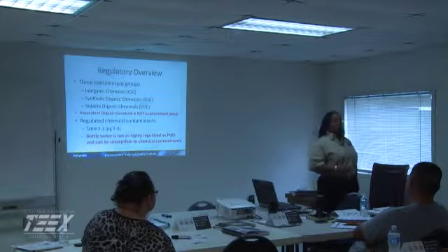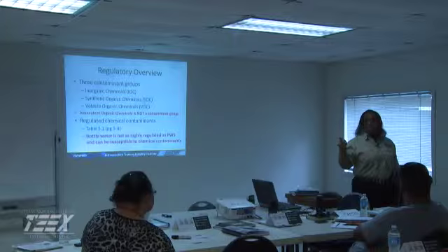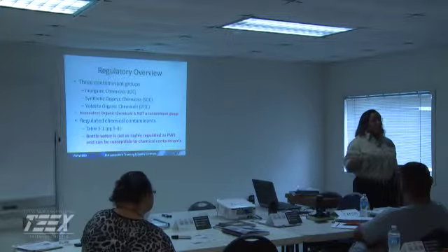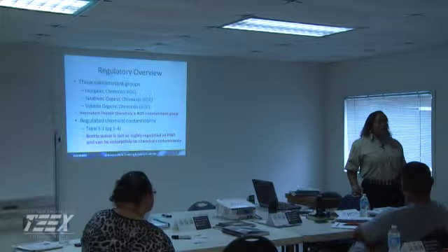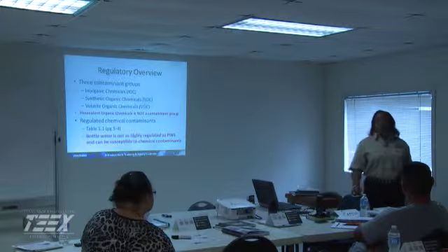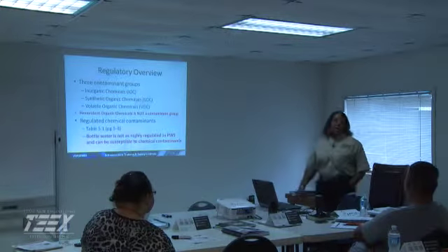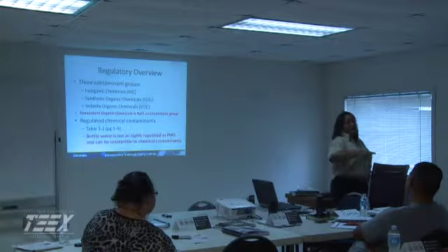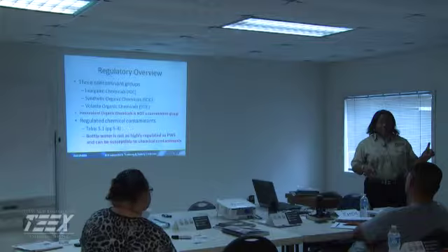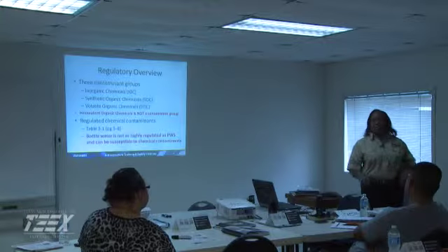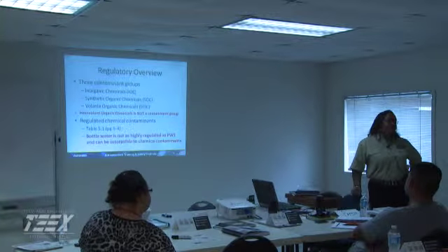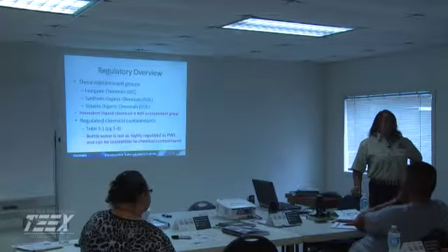I feel very strongly, and what we will see when we start getting into the membrane technology, if you want a pure water, one of the best technologies on the market today is RO, reverse osmosis. It can remove matter up to 0.001 microns, and no other systems that we have out there can reach that type of purity right now. So as long as we're checking the integrity of the membrane and it's being periodically cleaned, and we have that data to back that up, the water that's produced is of great quality, better quality than many other places. So if you all have a system where you have reverse osmosis, you're above the cut.